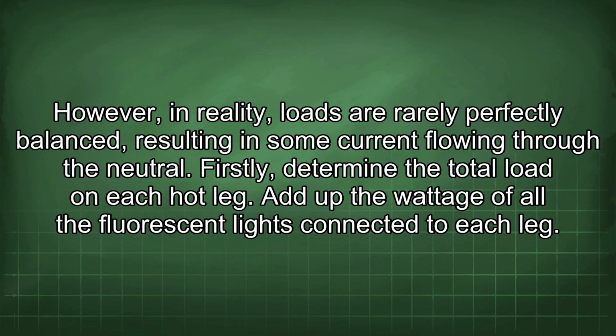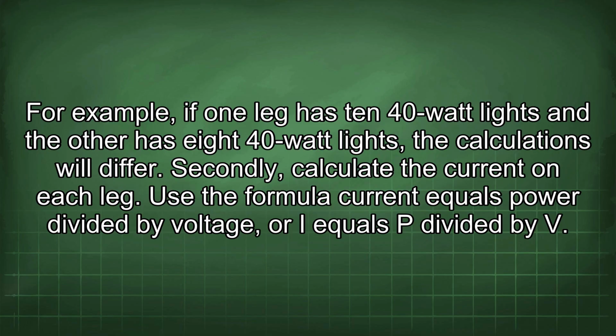Firstly, determine the total load on each hot leg. Add up the wattage of all the fluorescent lights connected to each leg. For example, if one leg has 10 40-watt lights and the other has 8 40-watt lights, the calculations will differ. Secondly, calculate the current on each leg. Use the formula current equals power divided by voltage, or I = P/V.